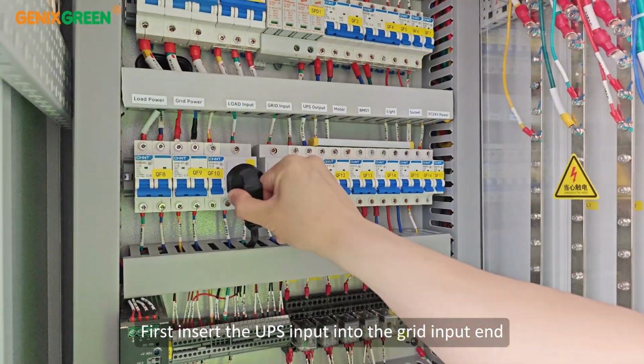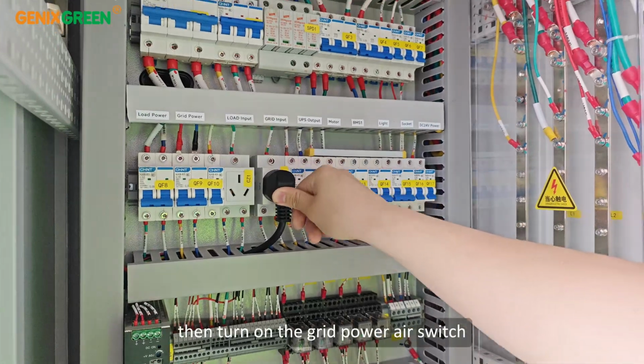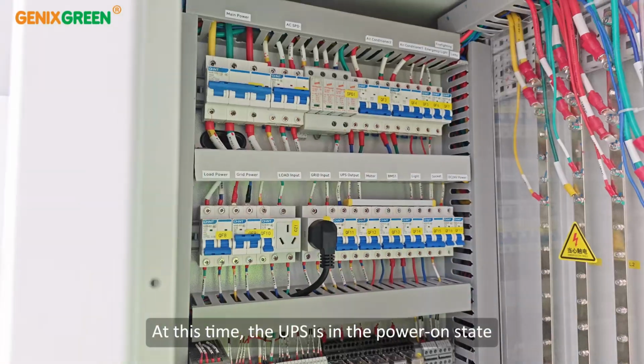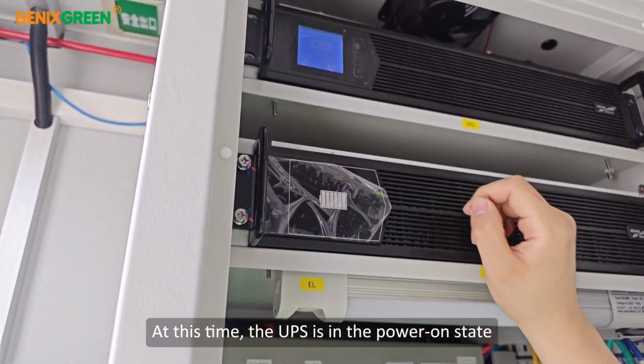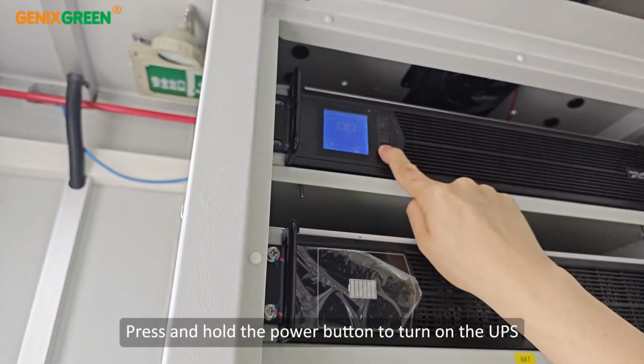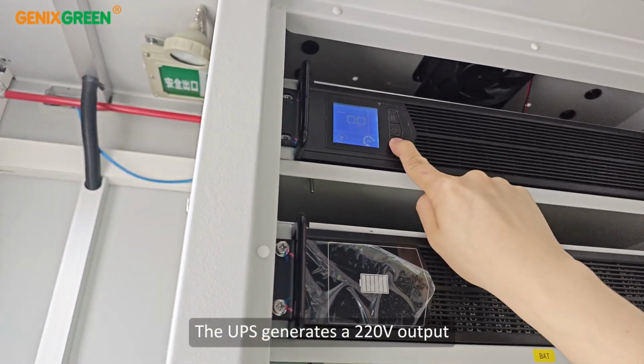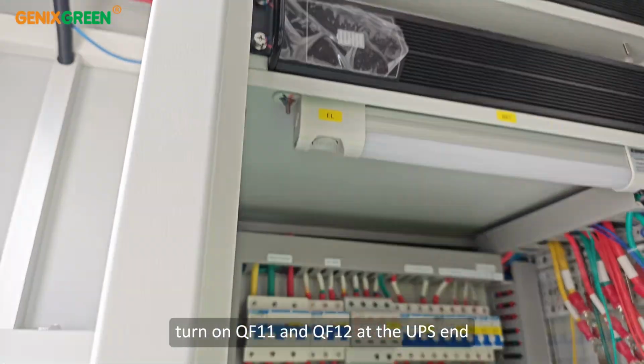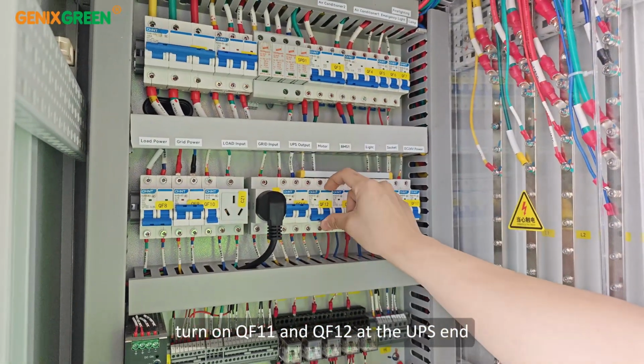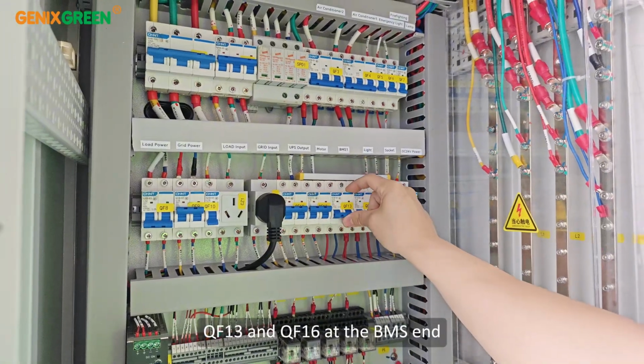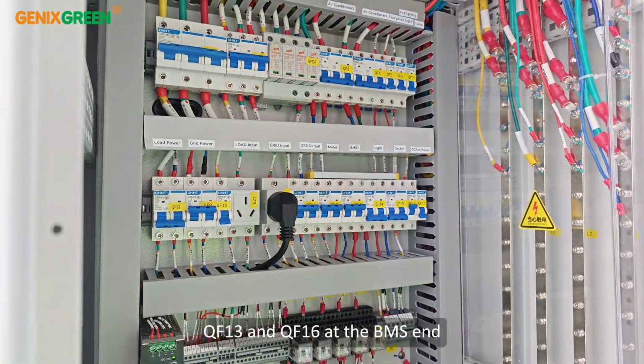First, insert the UPS input into the grid input end. Then turn on the grid power air switch. At this time, the UPS is in the power on state. Press and hold the power button to turn on the UPS. The UPS generates a 220V output. Turn on QF11 and QF12 at the UPS end, QF13 and QF16 at the BMS end.